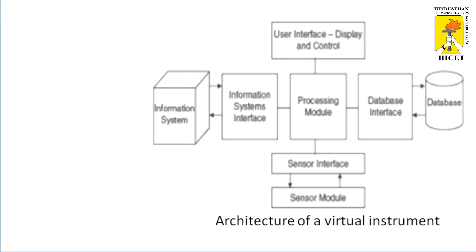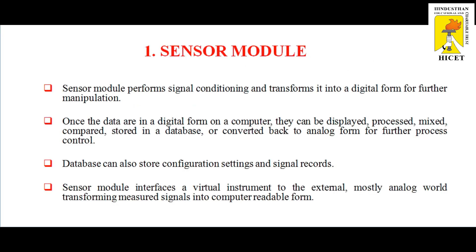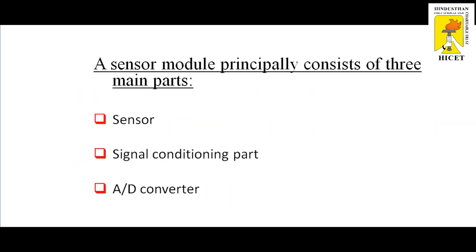First, we will see about the sensor module. The sensor module performs signal conditioning and transforms it into a digital form for further manipulation. Once the data are in digital form on a computer, they can be displayed, processed, mixed, compared, stored in a database, or converted back to an analog form for further process control. The database can also store configuration settings and signal records. The sensor module interfaces a virtual instrument to the external, mostly analog world, transforming measured signals into computer-readable form. A sensor module principally consists of three main parts: the sensor, the signal conditioning part, and the analog to digital converter.